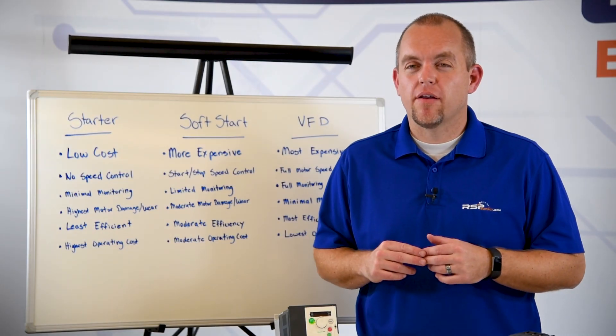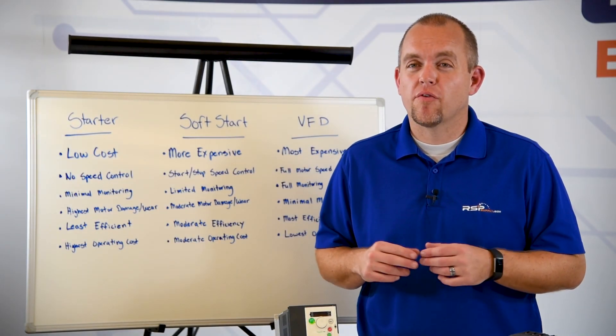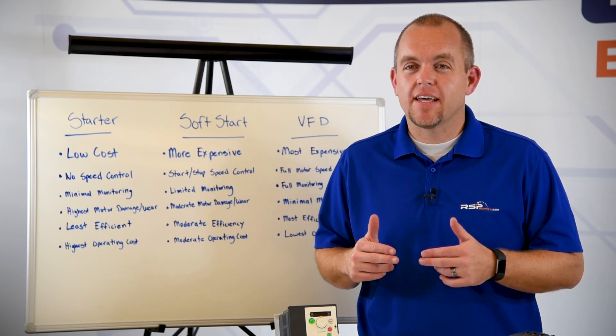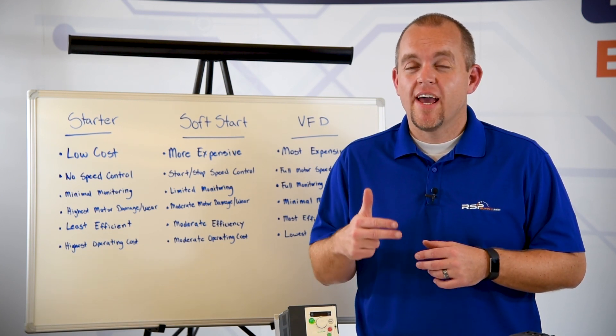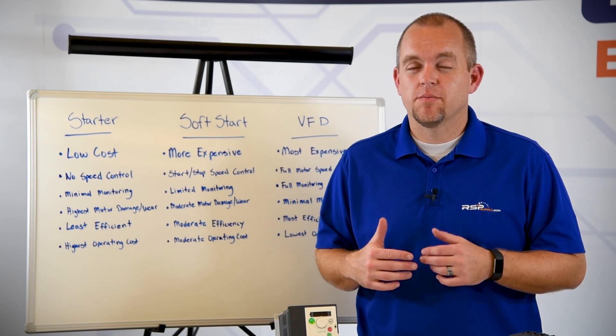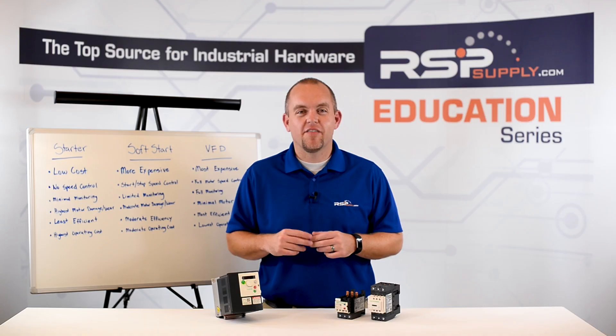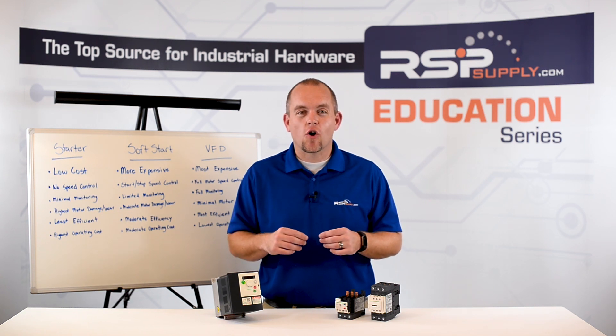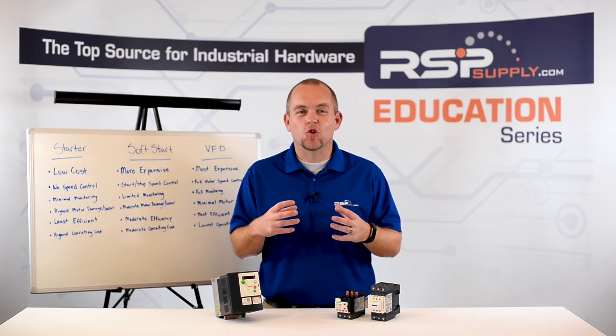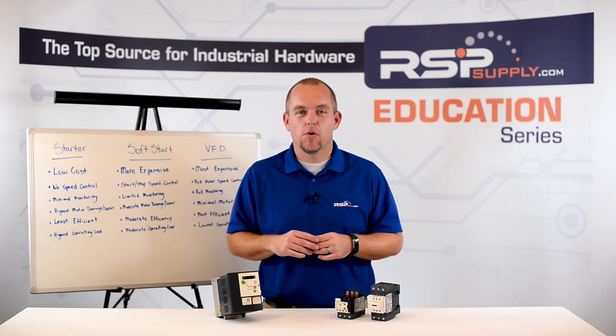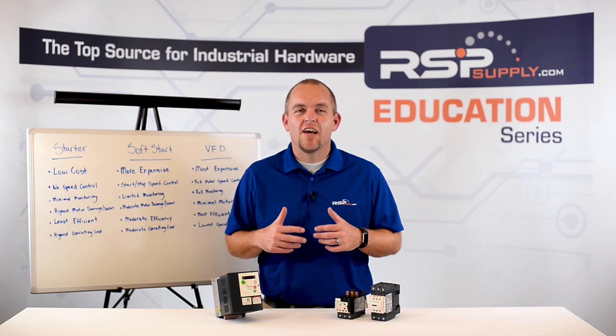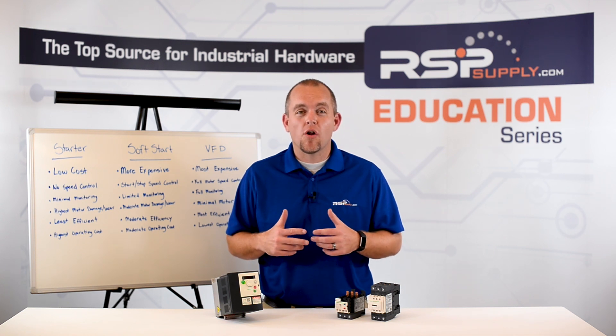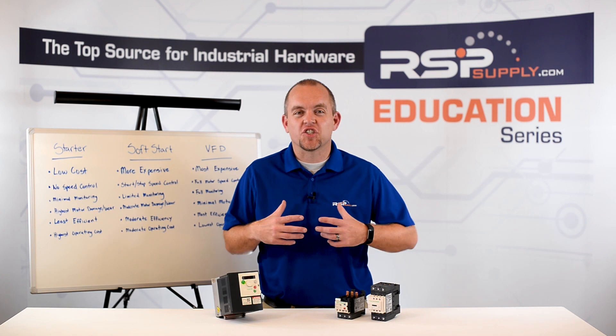Lastly, we are going to talk about VFDs, or variable frequency drives. A VFD provides all of the same functionality as both a starter and a soft starter, but also gives us some added functionality. A VFD gives us the ability to ramp up and down the speed of a motor during the start and stop function. It also gives us the ability to provide full speed control during the entire run cycle of the motor. Because of these efficiencies, VFDs allow us to run the motor at a much lower cost while also reducing wear and tear and stress on the motor.